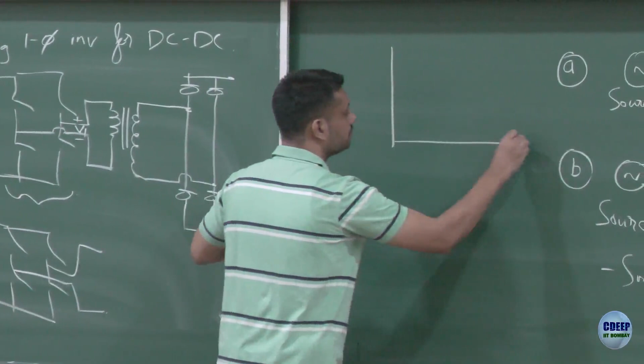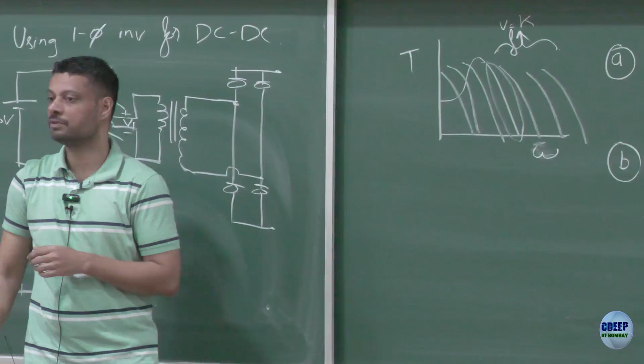So you're operating somewhere in this region with a fixed voltage and frequency. But with variable voltage and variable frequency, you can operate along different lines, or even go beyond. In this region, we keep the voltage constant but keep increasing the frequency, and that's called field weakening. So you can go to speeds beyond what's limited by the 50 hertz supply, because here you can have a fundamental of 60 hertz, even 70 hertz. So you can increase the speed.